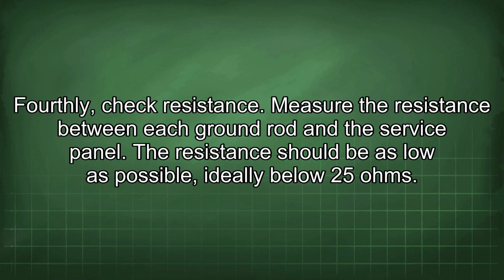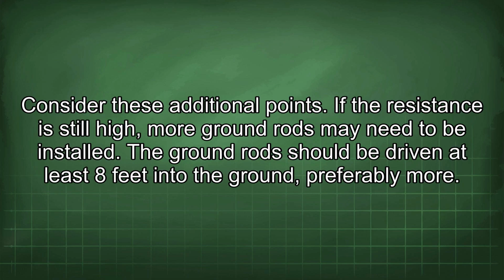Fourthly, check resistance. Measure the resistance between each ground rod and the service panel. The resistance should be as low as possible, ideally below 25 ohms. Consider these additional points. If the resistance is still high, more ground rods may need to be installed.